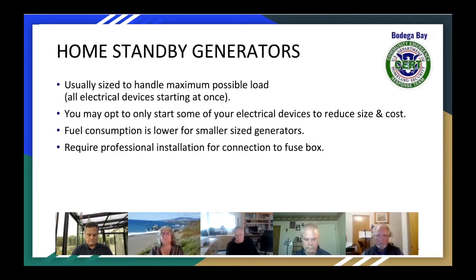The other thing to consider with smaller generators people try to plug into their house or tie in directly is making absolutely sure they cannot feed back into PG&E's system. As an electrician who did transmission and distribution, the transformers don't care which way the power comes in. If you energize the low side of a transformer, the high side becomes energized, and a worker on the line becomes susceptible to the 12,000 volts that appears on the primary side of that transformer.